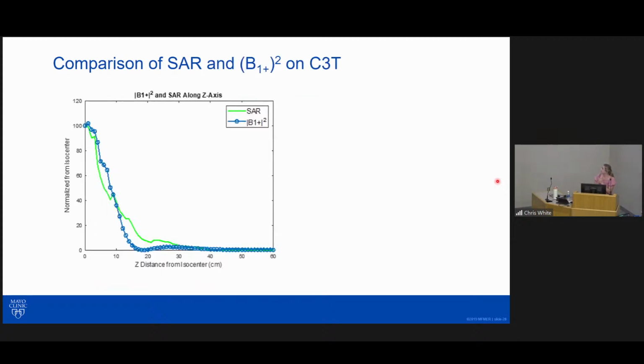The magnitude of the B1 plus squared field and SAR fall off rapidly on the compact 3T along the z-axis and are already reduced by an order of magnitude at a location 60 centimeters inferior to the head. Because this figure indicates that SAR falls off similarly to the B1 plus squared field, we know that we can use B1 plus squared independently to assess the RF.